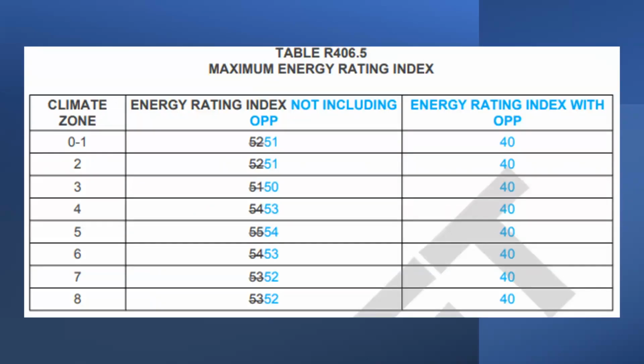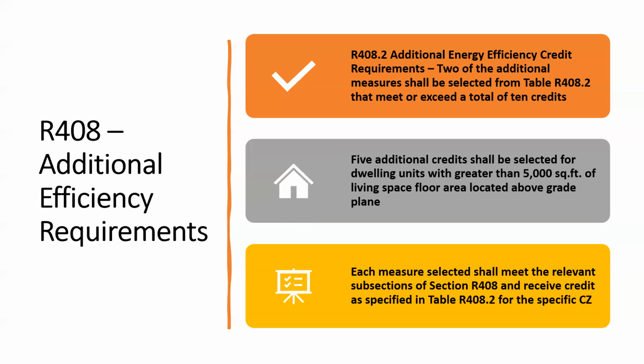So it did also adjust the ERI. In Texas, we have our own ERI to follow because House Bill 3215 adjusted the ERI for Texas. But if you read it straight out of the code book, it's dropping at least 1 to 2 points for ERI. What they did add, to the right, is another ERI number: if you're going to use on-site power generation or on-site power production, this is the ERI number you need to follow. Before, it always just said you can't get to the number in the middle column by using on-site power production. Now they're saying, if you're going to use power production, then this is the number you need to hit or be below in all climate zones. So without on-site power production, you're in the middle column. With on-site power production, you're in the right column, and you need to be 40 on the ERI or better in all climate zones. The additional efficiency, we just talked about why that was struck out, because it's been changed completely. You'll see what it looks like on the next table.